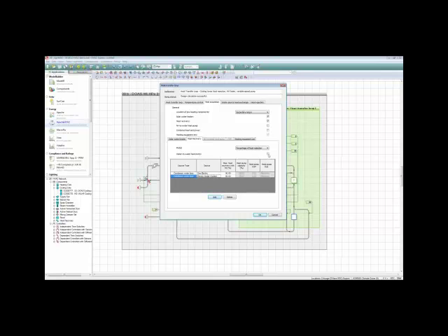Then I can opt for a heat pump, and this again is the simple model. Since I have multiple loops here, I just have a simple fixed COP value. If I go to the more sophisticated model of the explicit heat transfer, it's right away going to tell me that I'm going to reset the source data because I can only have one source. And so once I change that, I now have the ability to choose just one of those sources, but now I have an explicit heat exchanger between that condenser water loop and this heat transfer loop.